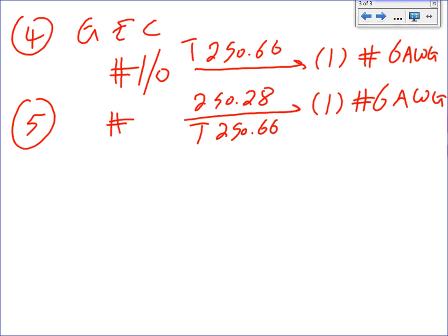Number 1 aught. And this is main bonding jumper. Yeah, you take the 1 aught exactly the same way, except to see what the reference is, I put 250.28, so it reminds you that at one time you might have 12.5%.